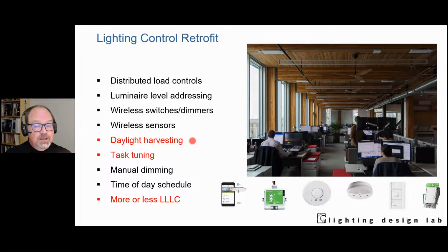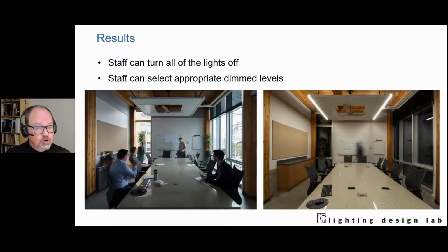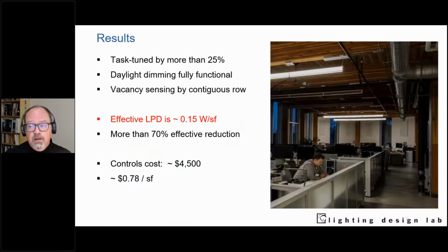We started to be able to do effective daylight harvesting. We were able to task tune down to the light level I initially wanted, along with scheduling and all of these things. The best part was that we could actually turn the lights off. In our conference room, we could turn the lights off when we wanted a conference without lights, because we had tons of daylight in that space. It made staff ecstatic to be able to control the lights the way they wanted. Ultimately we task tuned by more than 25%, with fully functional daylighting, and vacancy sensing was contiguous by row.